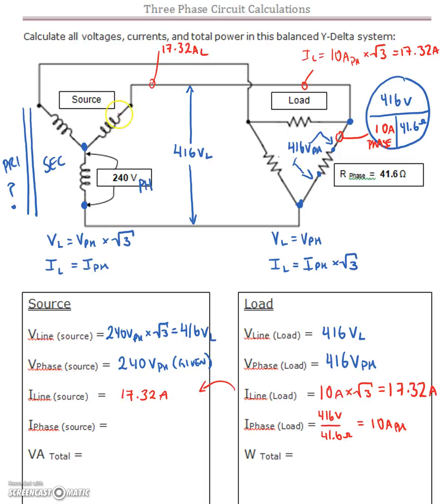And on the Y circuit, we can see that the current just has one path to go out from that transformer's winding. So on the inside, our phase current is also going to be 17.32 amps. So I phase is equal to I line for a Y is 17.32 amps on the inside. So each of these windings right here are responsible for 17.32. They come over here. That 17.32 comes in, and each of these loads are drawing 10 amps each, just 120 degrees apart in phase.